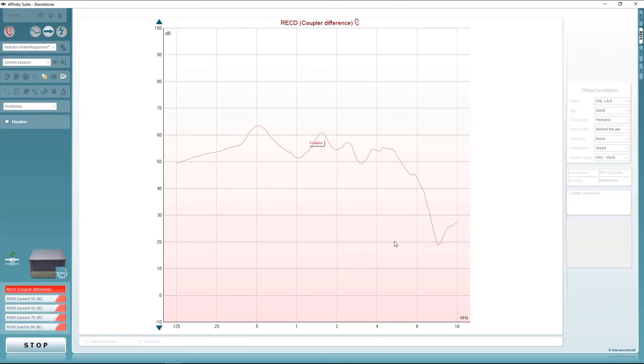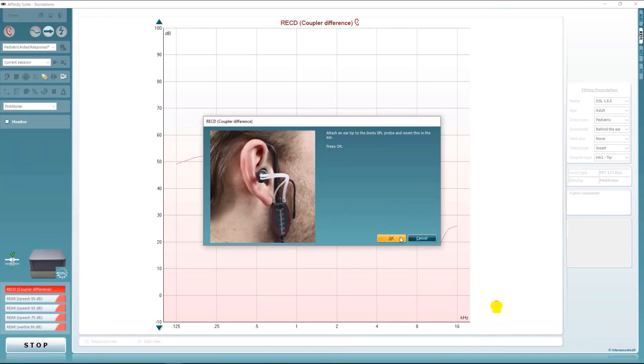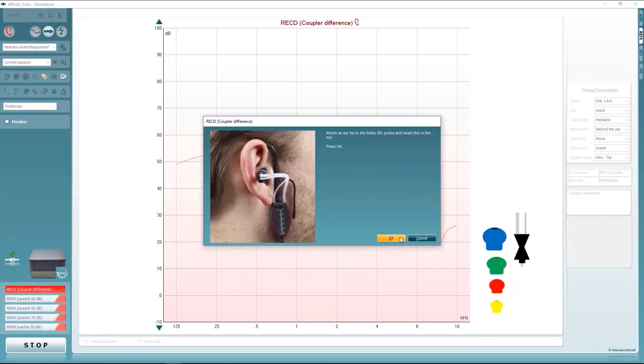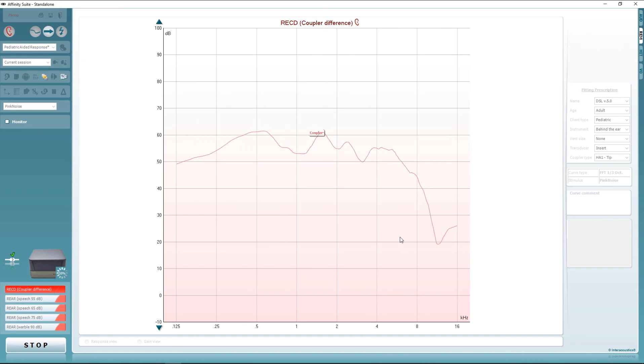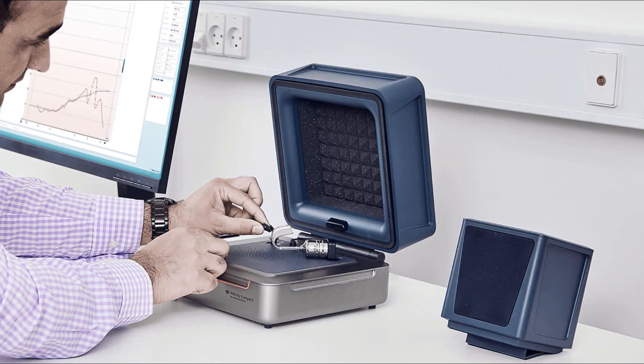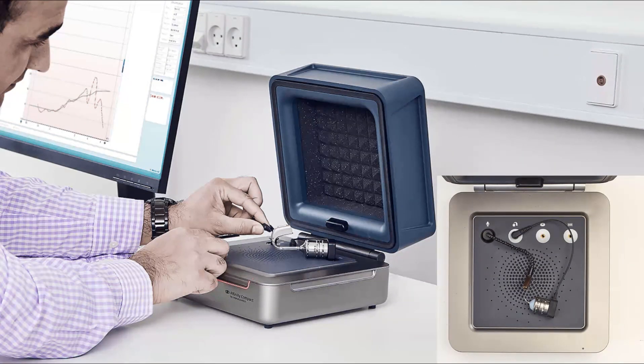The next measurement is the real ear measurement. Select an appropriate tip and attach this to the SPL60 probe — note that it uses the same tips as standard tympanometry. The real ear response is now measured and automatically subtracted from the coupler response, leaving the RECD, which can be seen at the bottom of the screen. You are now ready to fit the instrument by placing it in the test box and performing a real ear aided response measurement. When fitting using the SPL60 probe, the aided measurements in the test box must be recorded using a HA1 adapter connected to either a 2cc or 0.4cc coupler.